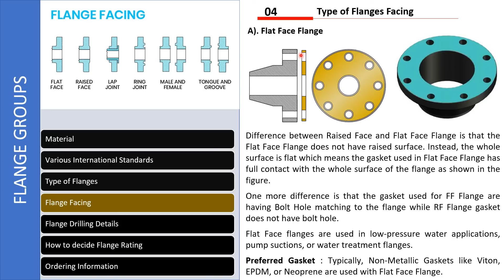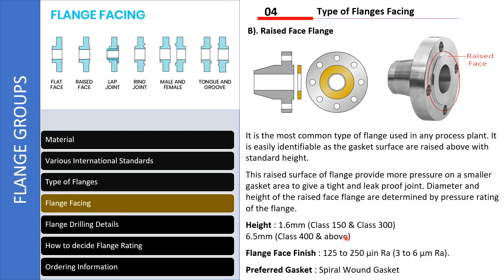Now, in case of a raised face flange, this is the face which is there on the flange. This is raised. So if you see, there is a projection over the surface. The height of this raised face is 1.5 to 1.6 mm up to 300 pound rating, and 6.5 above 300. These raised faces will be having a gasket which will be touching up to the raised face only. That means gaskets will not have bolts inside. These gaskets will be up to the raised face surface only. So it will always be between the flanges, inside the bolt diameter, and this will provide a very tight and leak proof joint. So diameter and height of the raised face are determined by the pressure rating. Based on pressure rating, the height of the raised face will keep on changing.